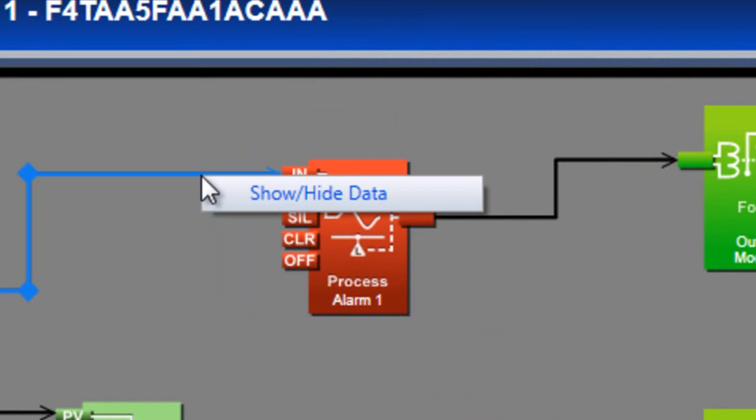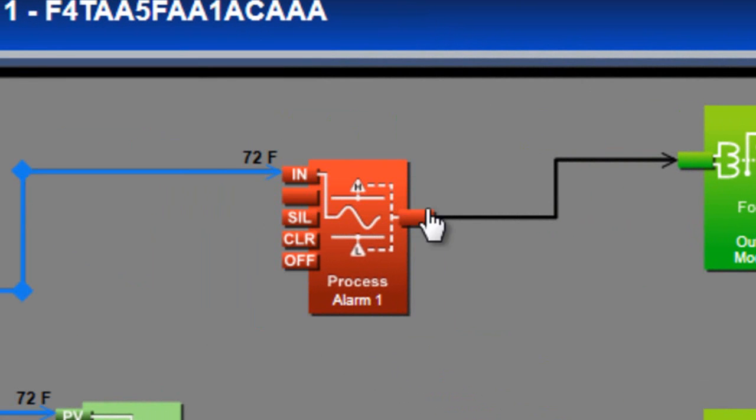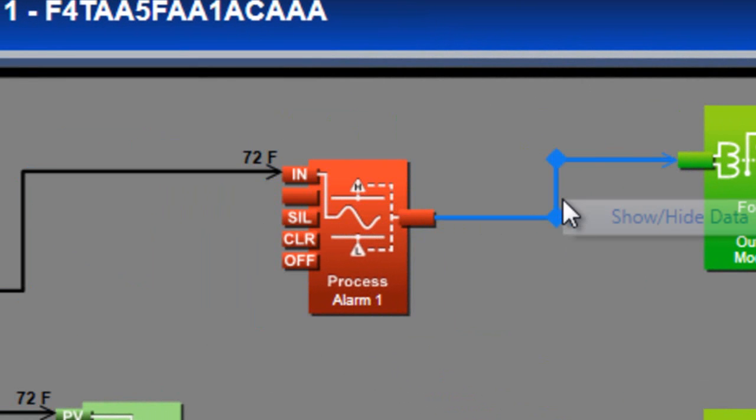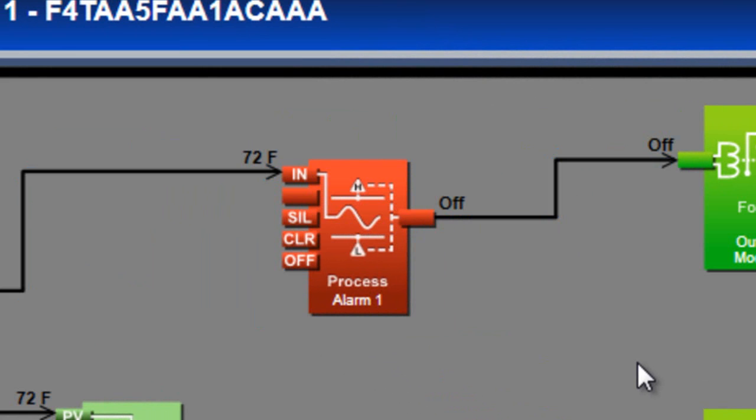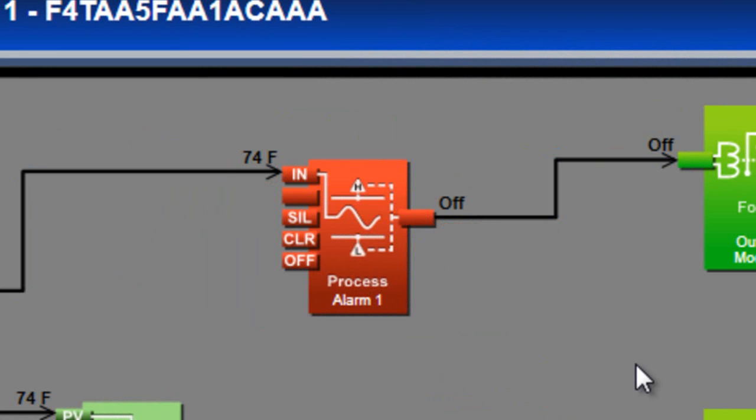By right-clicking the signals and selecting Show/Hide Data, we can monitor the signal values. When the temperature is below the alarm's high setpoint, the block's transmitter is off. When I raise the temperature to 75 or above, the transmitter turns on. When the temperature drops back down, the transmitter turns back off.